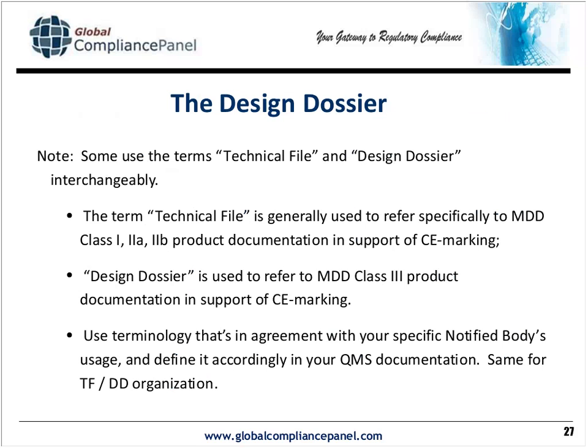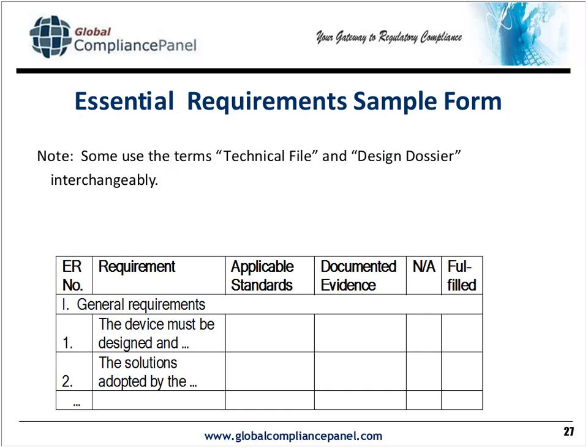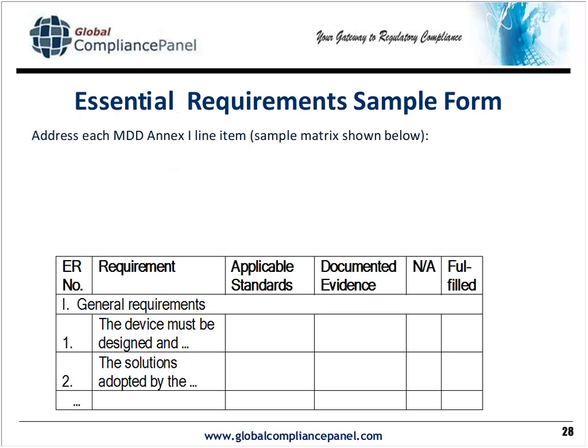Again, we've pretty well talked about the design dossier technical file. For essential requirements, I generally do a matrix here where I include every single requirement. I NA those that are not applicable.